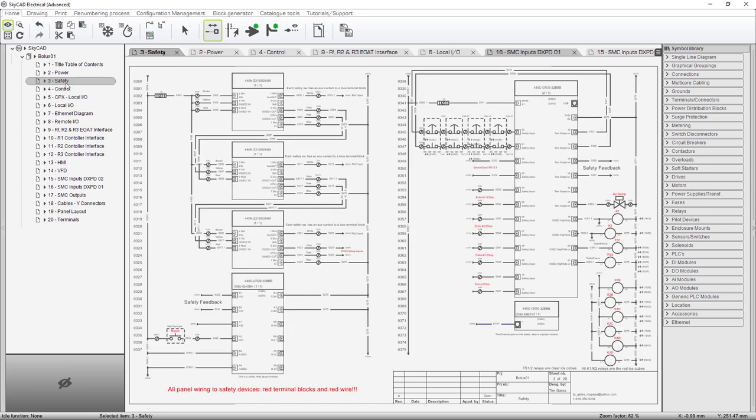Go to safety. We now have four e-stops in the string instead of two or three that we had before. And we may go back to just having three. But we added one on the door of the main control panel. And we have one on the HMI pendant. And then we have at least one on the other end of the machine. What you have to do is look at the layout of your machine and decide where they need to be. So the operator or someone who's watching can get there within a few seconds to hit it without having to walk all the way around something to get over there.